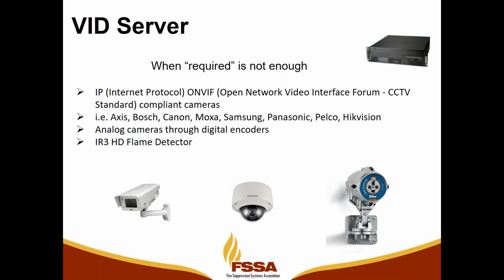Now, the new flame detector has an ONVIF HD video camera, so Ethernet can be run to it, to the server, and the analytics performed on the video on the detector. The detector is classified area, Class 1 Div 2, with a wide temperature range, negative, I believe, 67 degrees to 188 F. So when you put the detector in a classified area or a temperature rated area, you're also installing an HD camera that can be monitored with the analytics.